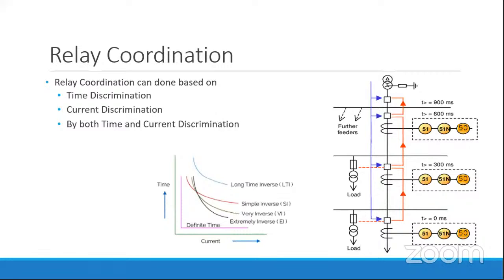Now for current discrimination, the feeder should operate for the minimum fault condition. As we go from upstream to downstream, the fault current will be lesser compared to upstream, because of the impedance of the equipment or cables connected to the network at which the fault occurs. So we can say the fault current at this particular network will be lesser, and for the upstream network it will be much higher.